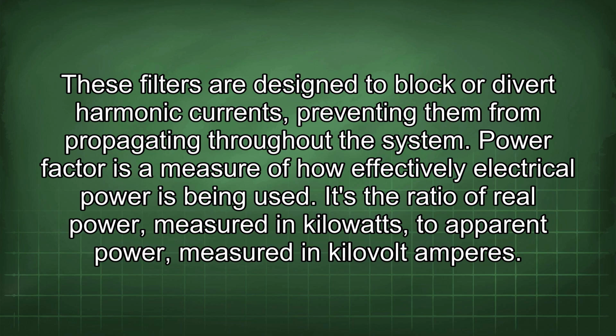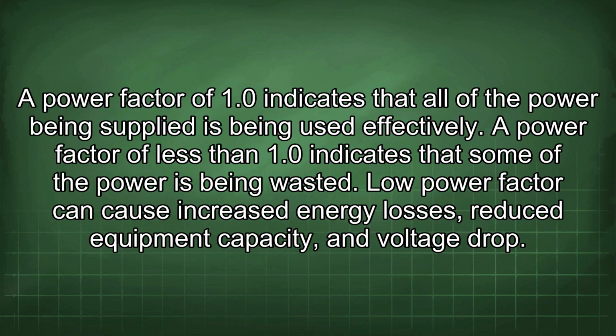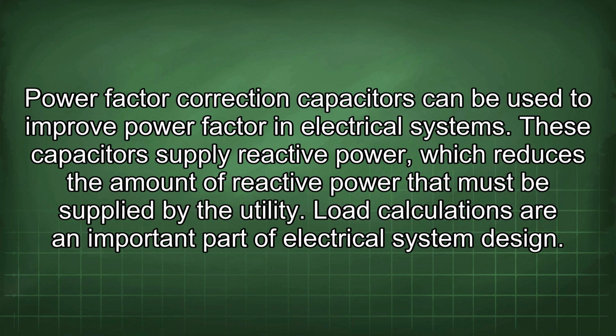Power factor is a measure of how effective the electrical power is being used. It's the ratio of real power, measured in kilowatts, to apparent power, measured in kilovolt amperes. A power factor of 1.0 indicates that all of the power being supplied is being used effectively. A power factor of less than 1.0 indicates that some of the power is being wasted. Low power factor can cause increased energy losses, reduced equipment capacity, and voltage drop. Power factor correction capacitors can be used to improve power factor in electrical systems. These capacitors supply reactive power, which reduces the amount of reactive power that must be supplied by the utility.